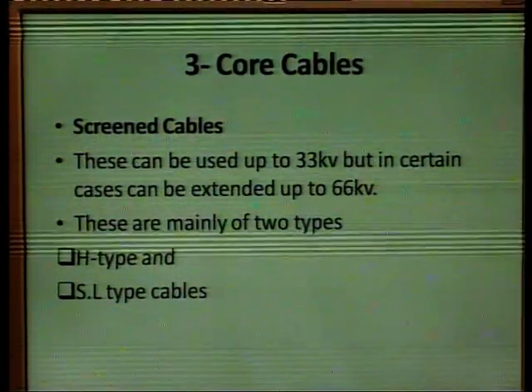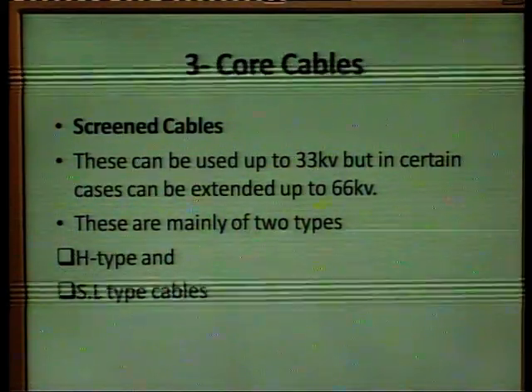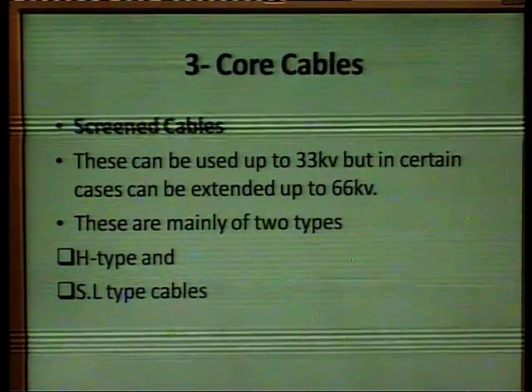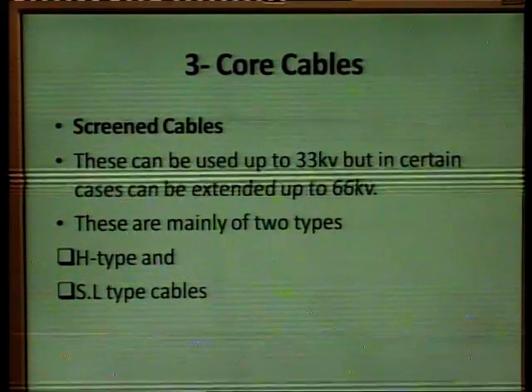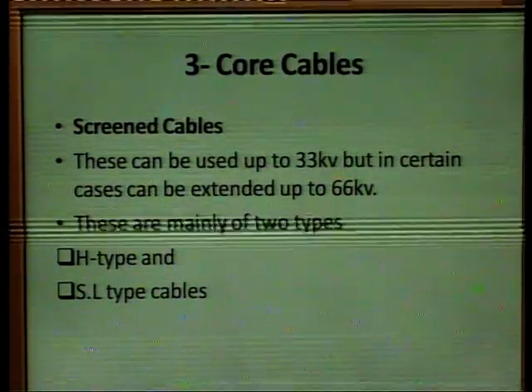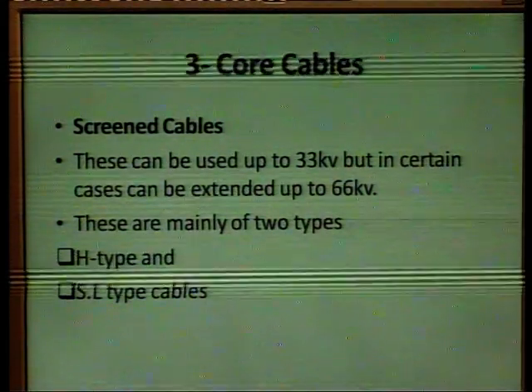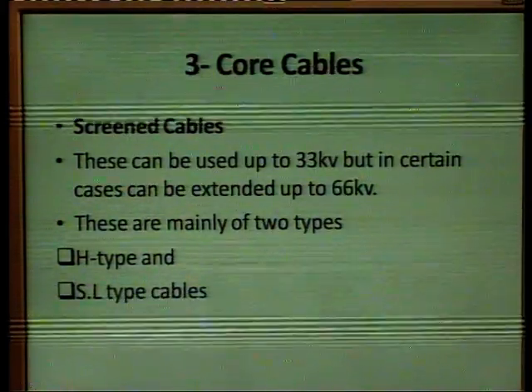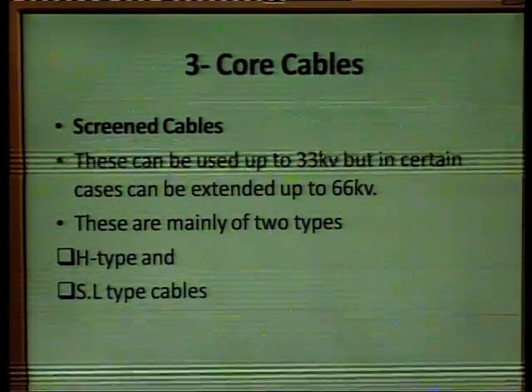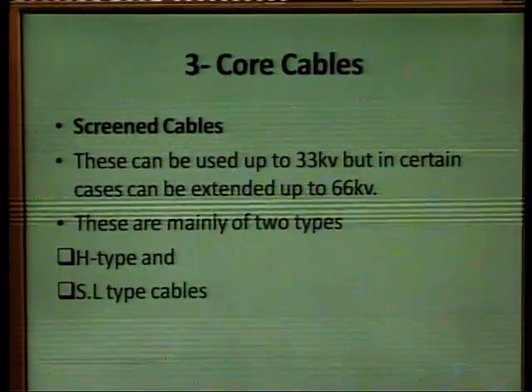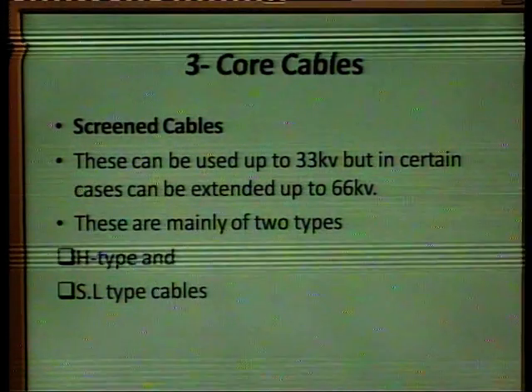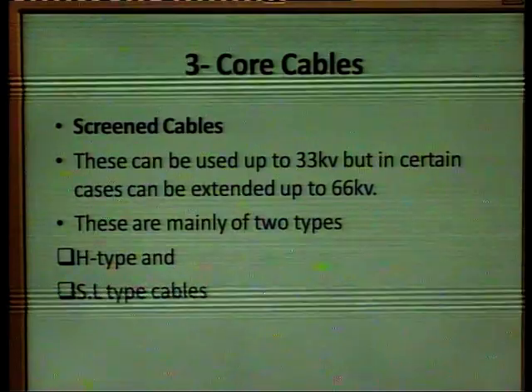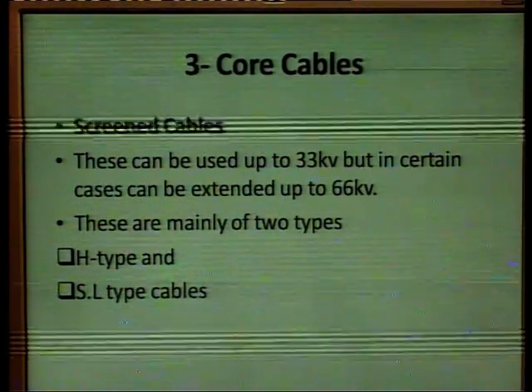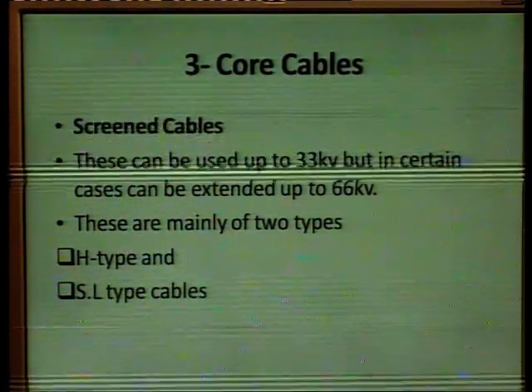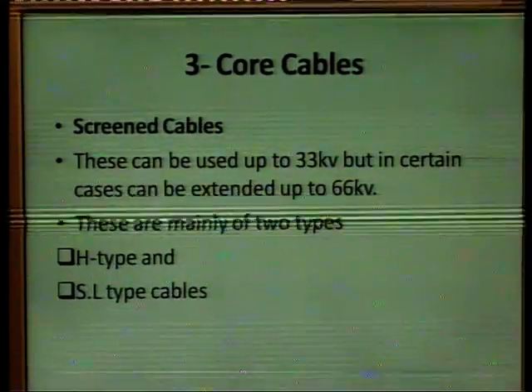Then in the 3 core cables category, we have the screened cables. Now these can be used up to 33 kV, but in certain cases these can be extended up to 66 kV. So they are mainly of 2 types. First is H type, then SL type cables.